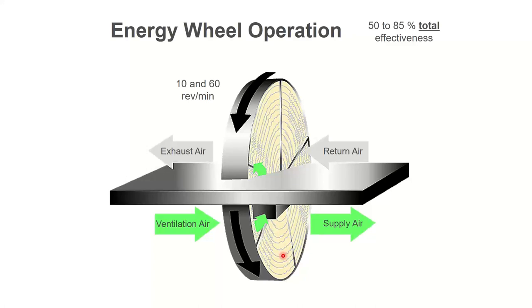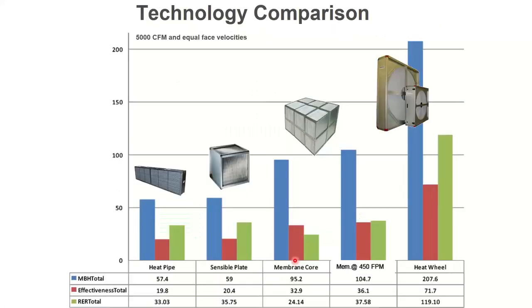You can do some stuff with frost control by changing the wheel speed. On simple ERVs, you won't do that, but on more complex air handlers, you would. And this can also be a sensible only or a sensible plus latent version. Most of them are latent. The way these do the latent is the plastic media of the wheel is impregnated with a silica gel. That's like those little packets you get in your leather shoe box or in your electronics boxes. It says silica gel, do not eat. That's in the box to absorb moisture and release moisture to keep the shoe box neutral when it gets shipped all over the place. That same material is on this media and it'll absorb moisture in this airstream and rotate to the other airstream that's drier and release it, and it always goes from the moist to the dry airstream. And which airstream is which changes with the season, but the way it works doesn't change.